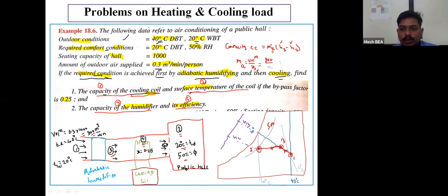After getting all those values, put them into this equation and I will get the capacity of cooling coil. The unit will be kg per minute into kilojoule per kg, so the final unit will be kilojoule per minute. This is how I get the value of capacity of cooling coil.